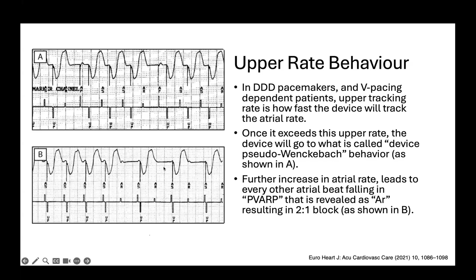But if the atrial rate goes beyond this, then every other atrial beat will fall in the PVARP, and this is revealed, as we see here, as the atrial refractory beat, and in that way, it looks like maybe the device is going into 2-to-1 block. So this might look like the device is not functioning well, but it's actually one of the programming features that the device uses to minimize pacing of the ventricle.